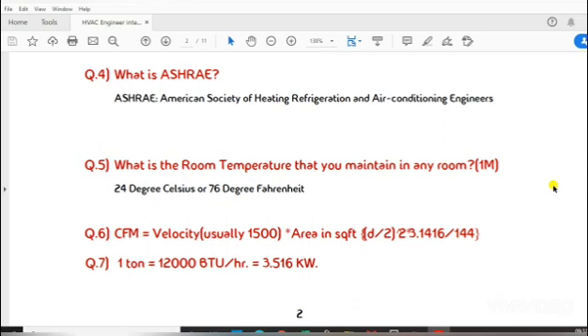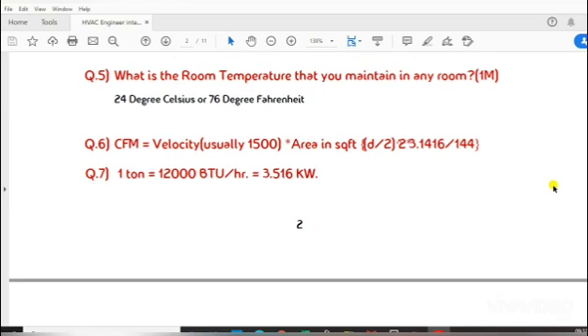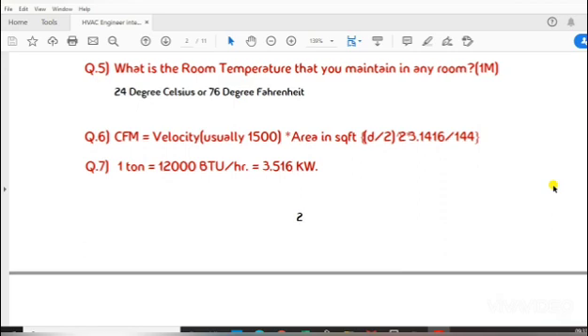Question 6: CFM equals velocity, usually 1,500, times area in square feet. Question 7: 1 ton equals 12,000 BTU/hour equals 3.516 kilowatt.